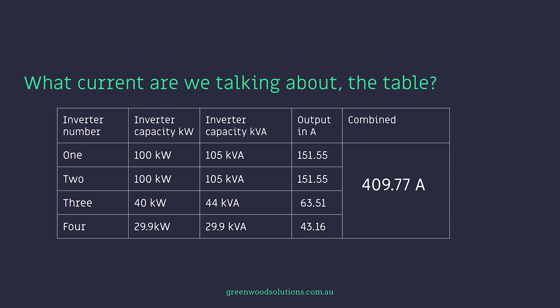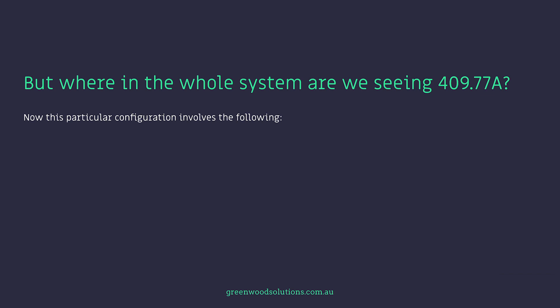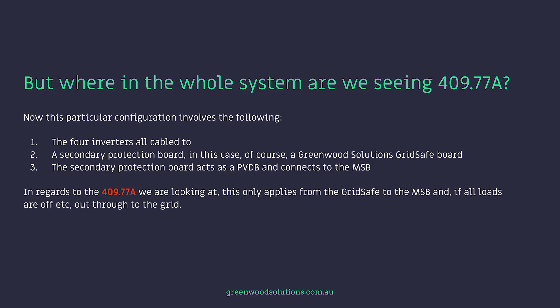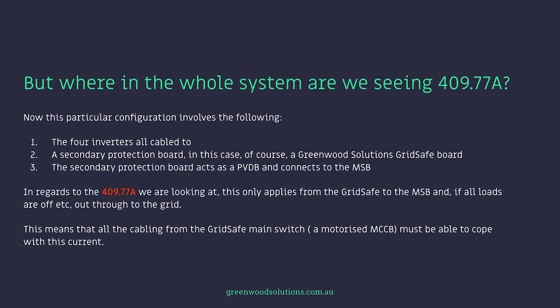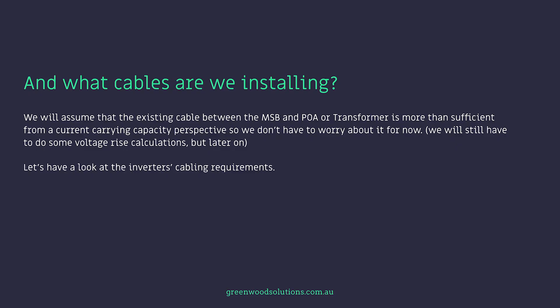Here are the results in a table — inverter one at 100kW/105kVA, inverter two, three, and four — combined total of 409.77 amps. But where in the whole system are we seeing 409.77 amps? This particular configuration has the four inverters all cabled to a secondary protection board — a Greenwood Solutions grid safe board. The secondary protection board acts as a PVDB and connects to the main switchboard. The 409.77 amps only applies from the grid safe to the MSB and if all loads are off, out through to the grid. We will assume the existing cable between the MSB and the transformer is more than sufficient from a current carrying capacity perspective, though we will still have to do some volt rise calculations later.